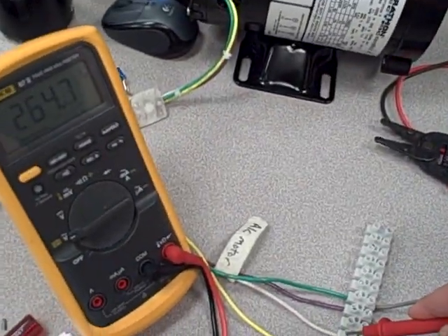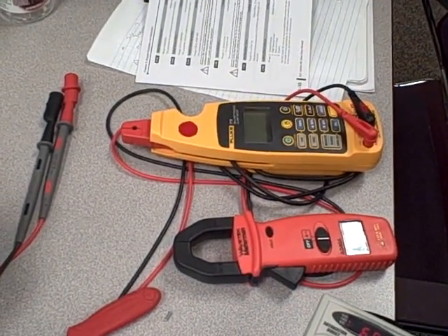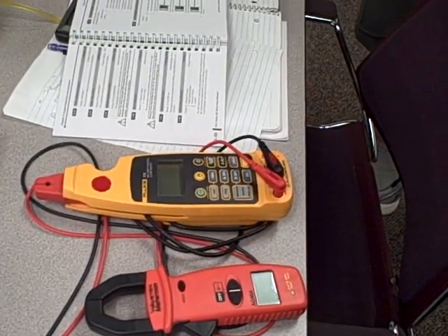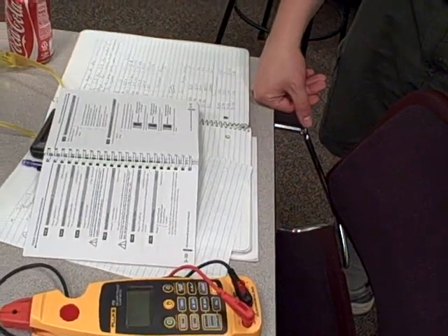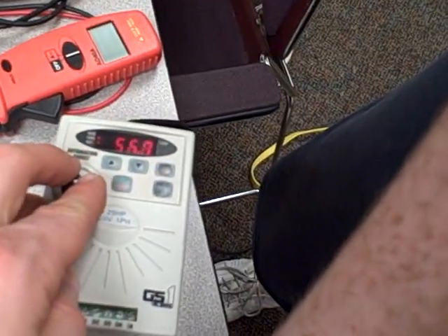We can actually calculate volts per hertz. And if we do that, go ahead and get your calculator out, do a quick calculation. Okay. Yeah, it looks like at 60 hertz, 4.4 is our V/F. Oh yeah, we calculated that earlier. Okay, so I'm going to take this and lower this to 50 hertz.